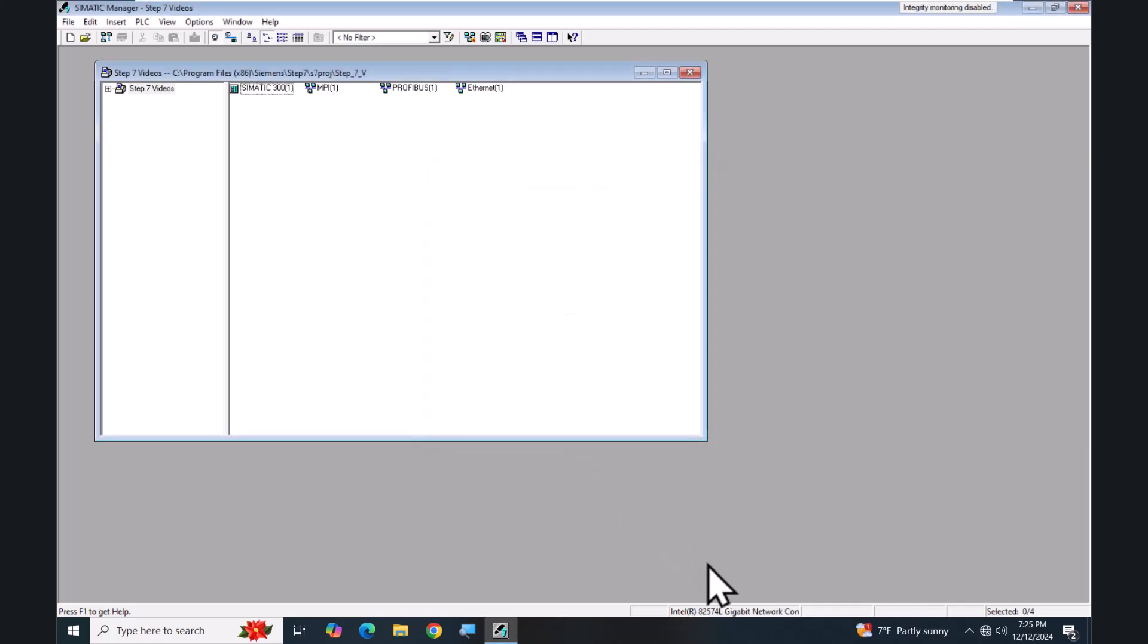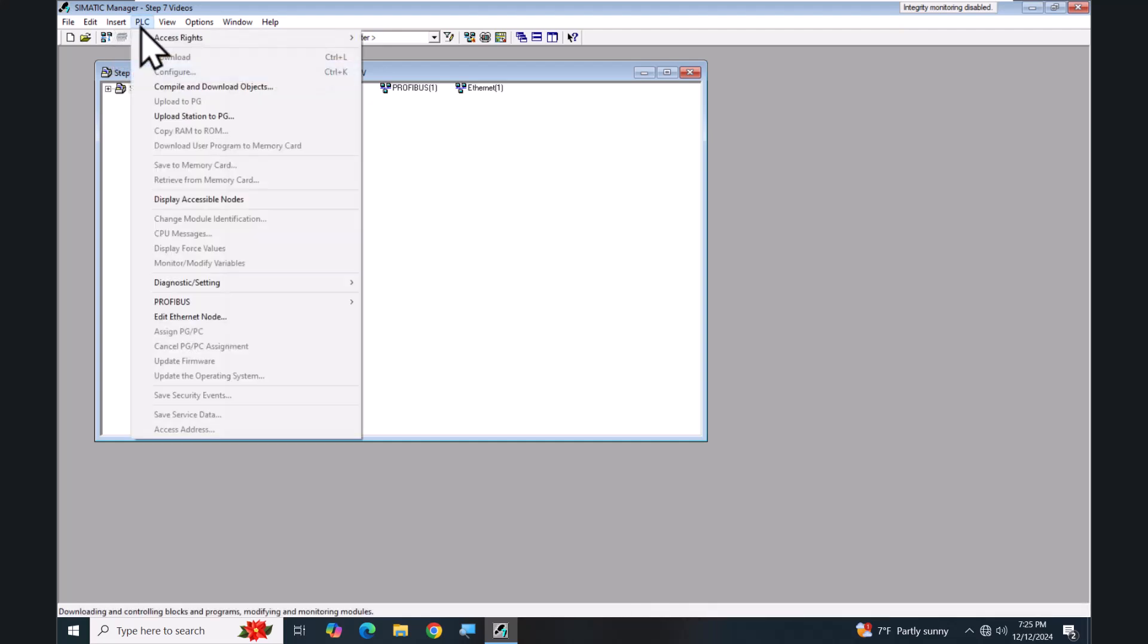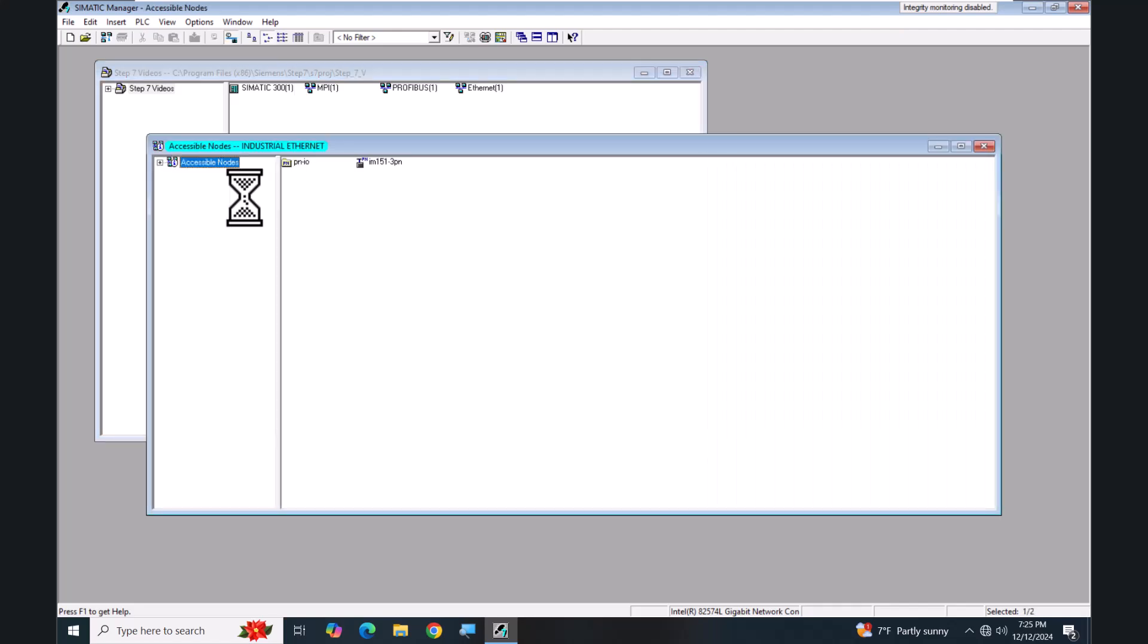Down in the status bar, if I hover over, I can actually see which network adapter is selected and assigned to my S7 Online logical interface. Now I will select Display Accessible Nodes. This time I will select the PLC menu and pick Display Accessible Nodes, so I can do it via the toolbar or via the PLC menu. So now I'm looking at Accessible Nodes via Ethernet. This is a low-level search below IP addresses. In this view I just have the small icon view so I don't get much information about my particular devices.